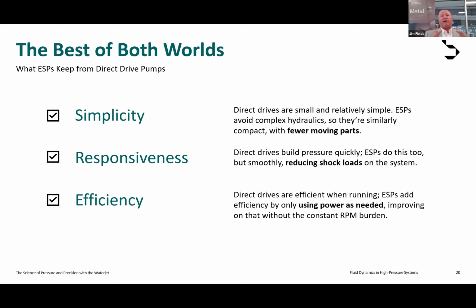Direct drives are very efficient when the jet is on. When you start adding on-off cycles, they rapidly become inefficient, so it's important to understand that. Deadheading bad, jet running good.